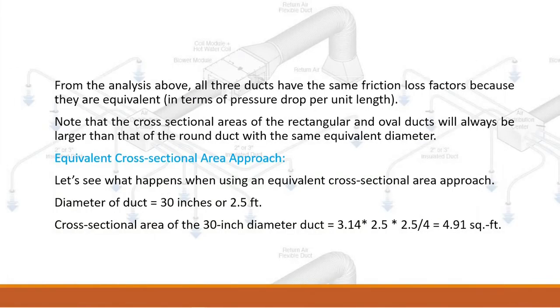From the analysis, all three ducts have the same friction loss factors because they are equivalent in terms of pressure drop per unit length. Note that the cross-sectional areas of the rectangular and oval ducts will always be larger than that of the round duct with the same equivalent diameter.